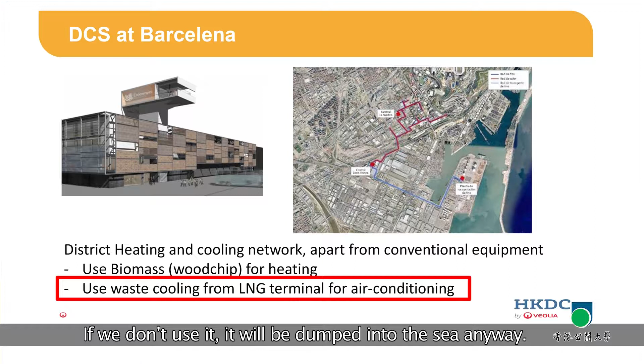There's another interesting project we have in Kuala Lumpur. It's a gas project using a gas turbine, which drives electricity to drive the electric chillers. They also use waste steam to drive chillers—a steam-driven centrifugal chiller instead of a motor. If you know electricity well, a gas turbine needs a stable load, so at nighttime when consumption isn't high, we use the electricity to produce ice. That makes the system more efficient.